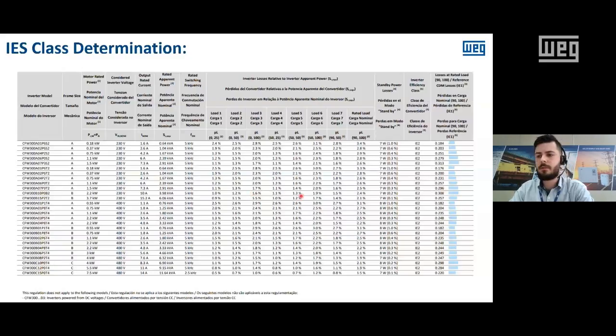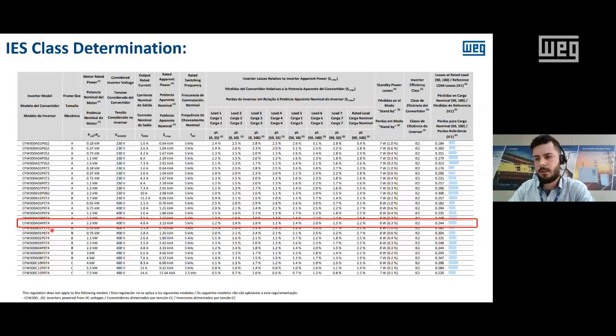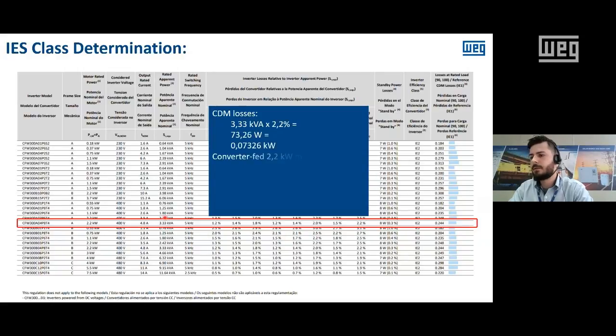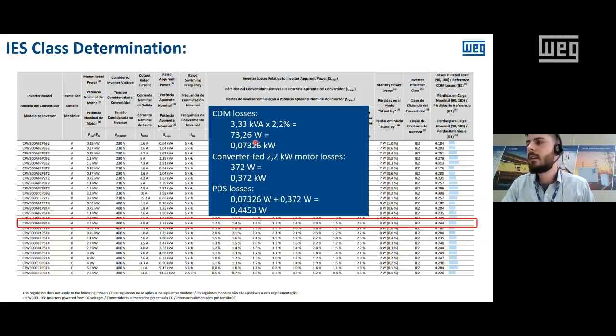A similar calculation can be done for power drive systems. And here, the class is not IE, but IES. Let's make an example here. I'm going to use the same drive for easy reference: the CFW300, 4.8 amperes, 400 volts for a 2.2 kilowatt motor. And the losses, as you remember, are 2.2% of the rated apparent power. If we calculate, the losses are going to be 73.26 watts. And here is one interesting thing.